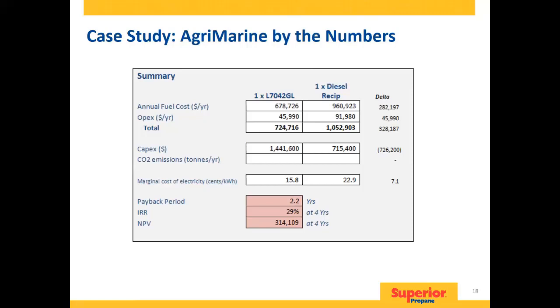The comparison you're seeing on the screen is for a new propane powered generator against a new tier certified diesel generator in 2016. The propane solution provides an annual operating cost savings of approximately $328,000 related to both fuel and maintenance. Assuming the spread between the fuels stays the same, in 2.2 years the savings covers the difference in cost of the propane power generator, and in the next approximate 2.2 years, the generator pays for itself entirely with the savings. In the meantime, the diesel generator continues to have an operating cost $328,000 higher than the propane unit.